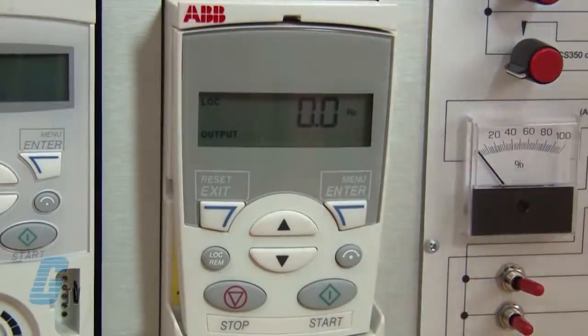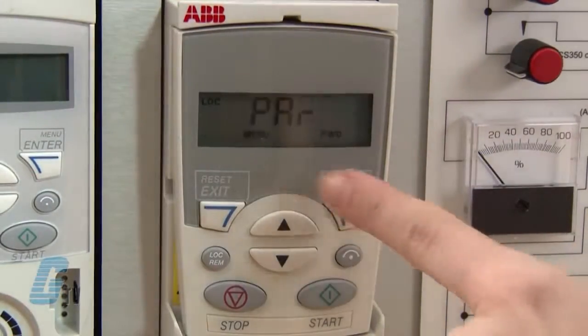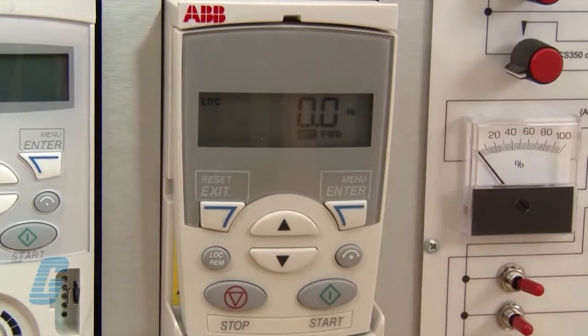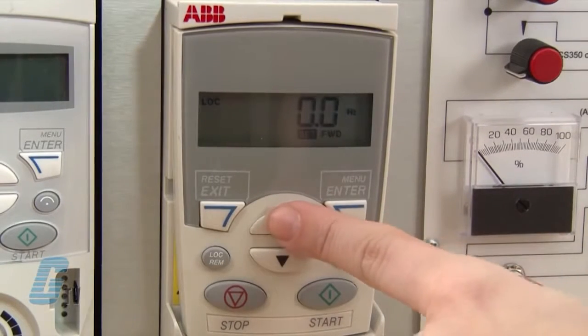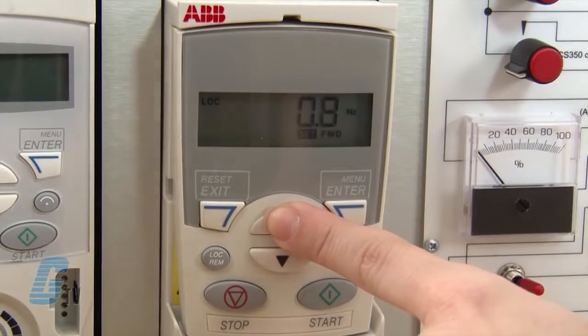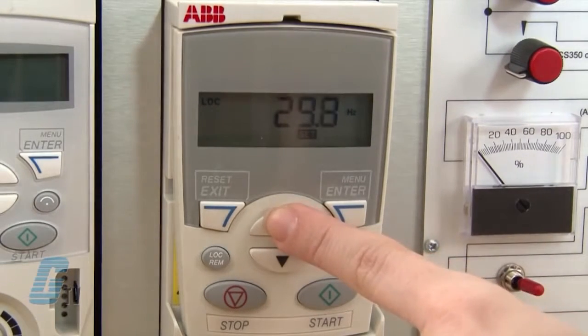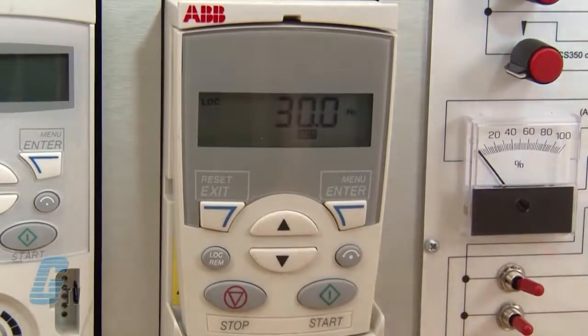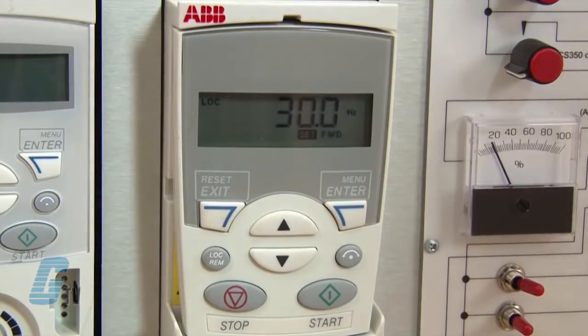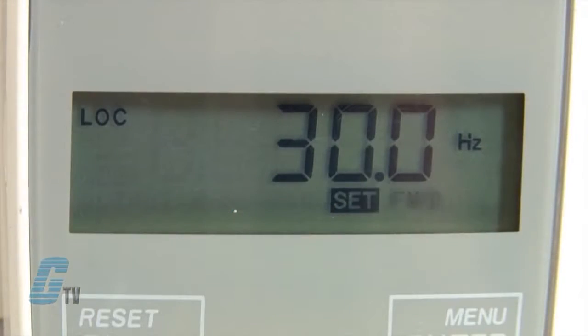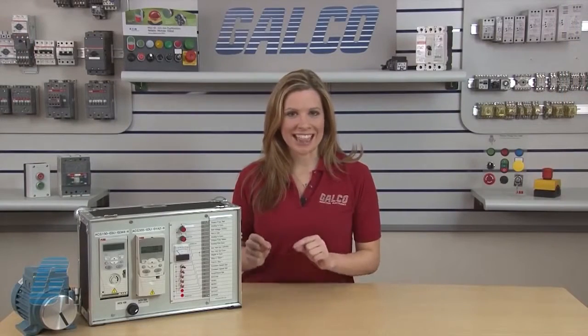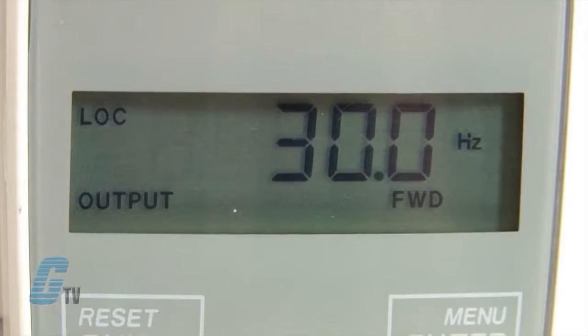Now I'll go into the reference mode by pushing the menu key and then scroll to REF and press the Enter key. I can now push the up arrow for my desired speed and then push the Start button. The bottom should flash forward until it reaches the set point. Once the desired speed is achieved, the forward will turn into a steady on. By pushing on the arrow keys in the output screen, I can check the speed, current drawn, and the percentage of torque the motor is producing.